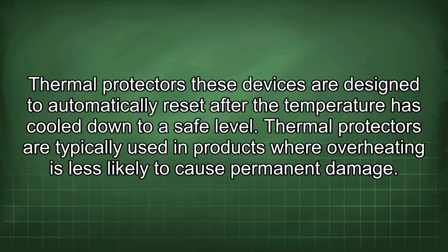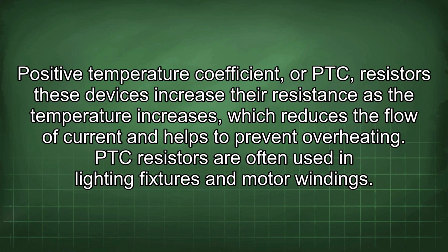Thermal protectors. These devices are designed to automatically reset after the temperature has cooled down to a safe level. Thermal protectors are typically used in products where overheating is less likely to cause permanent damage. Positive temperature coefficient, or PTC, resistors. These devices increase their resistance as the temperature increases, which reduces the flow of current and helps to prevent overheating. PTC resistors are often used in lighting fixtures and motor windings.